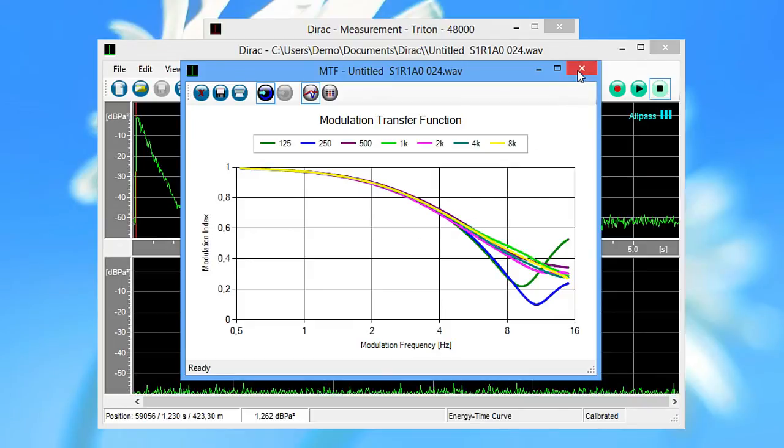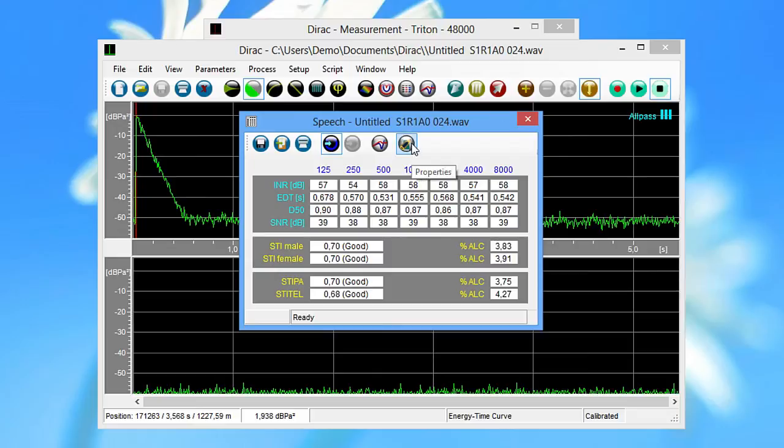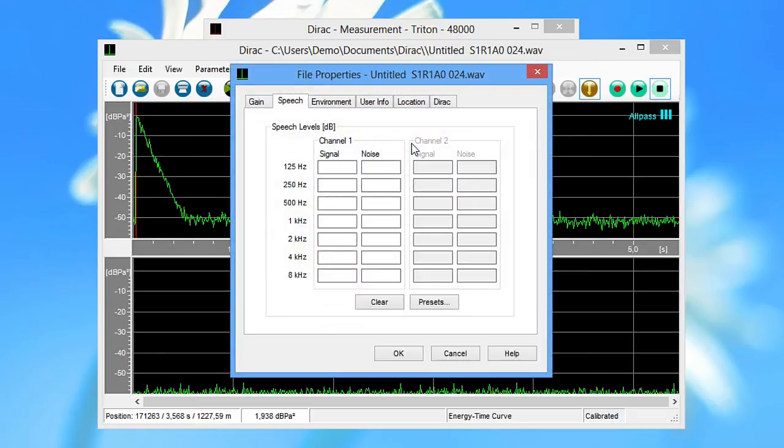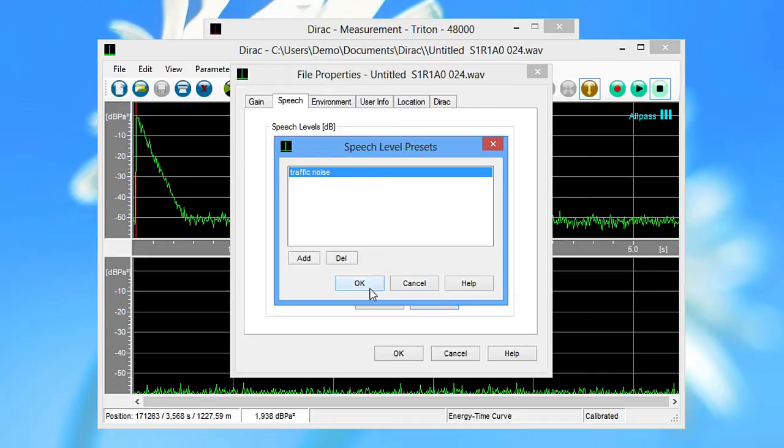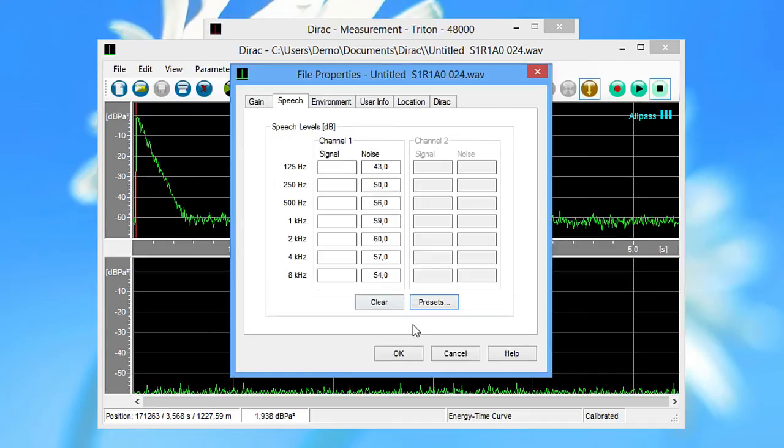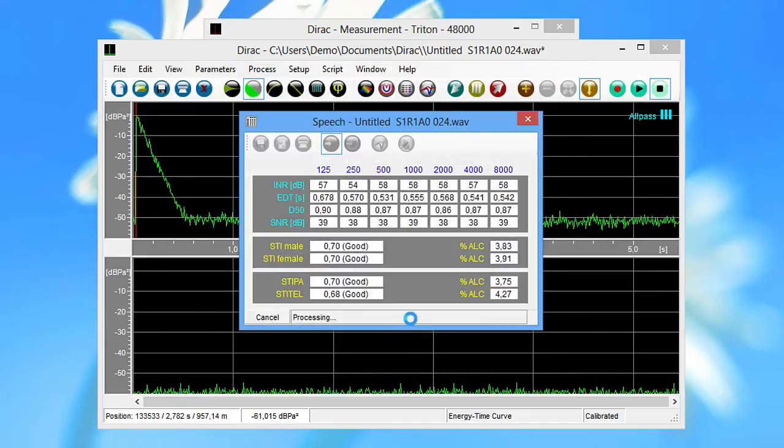Now suppose you want to see how the STI would differ if there was background noise from road traffic. For this, open the file properties window to set the noise levels manually on the speech tab. You can also use a previously measured traffic noise background. When you click OK, the STI is recalculated.